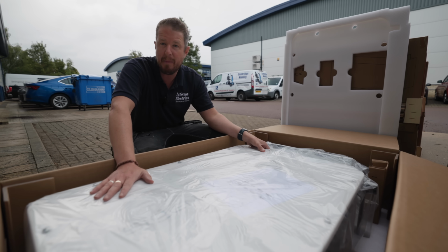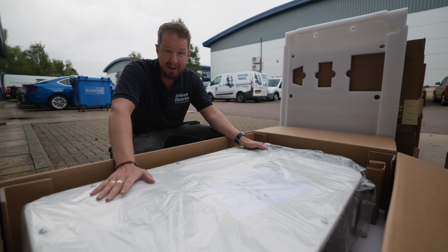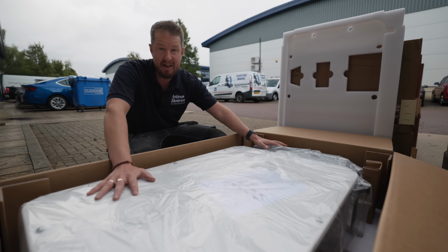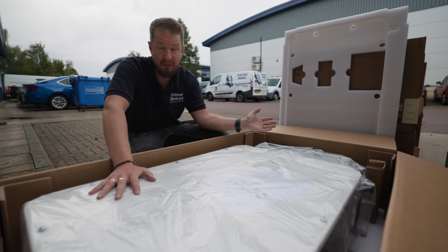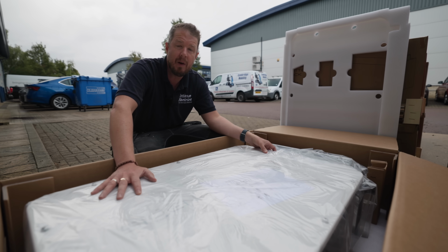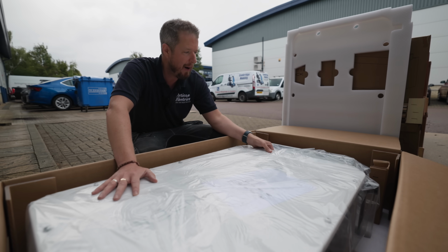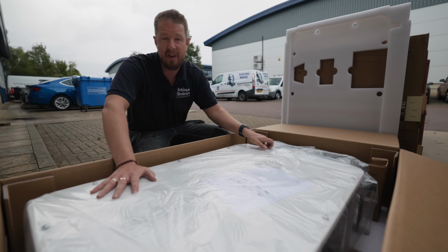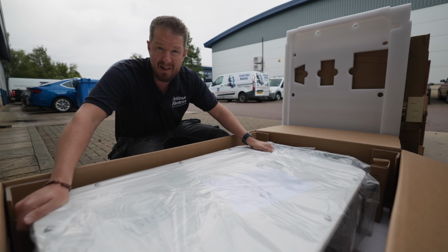And the reason we need such a big inverter is because the whole building power has to run through this, because the inverter acts as the gateway to provide instantaneous switch over to backup power from the batteries in the event of a power cut. All of that power is going to go through this box here. So it's a bit of a beast, but it's what we need.